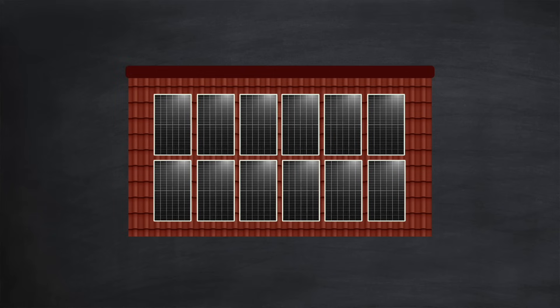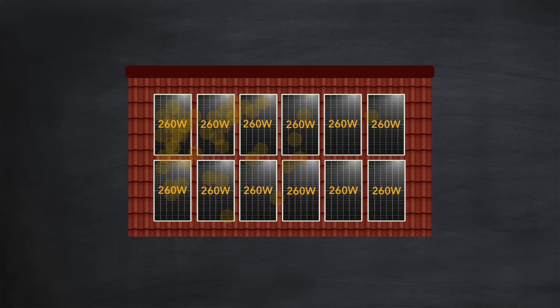Shading is certainly one of the main reasons people choose to have optimizers in their solar installations. But what are the other benefits? The accumulation of dirt over time can adversely affect array performance. In this example, you can see that over a year or two, dirt has accumulated towards the top left-hand side of the array. The dirtiest panel on the top left is now only able to output a maximum of 260 watts. If all the panels are connected to a string inverter without optimizers, for the same reasons we saw with shading, the maximum power output on each of the other panels would also be limited to 260 watts. However, if optimizers are fitted, they will ensure that each panel is able to output at its maximum level, despite the dirt.